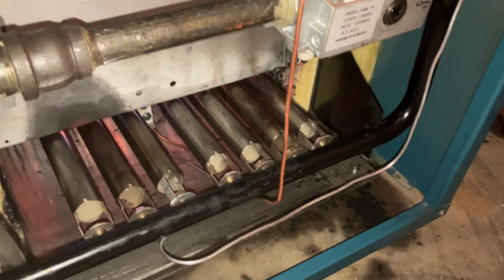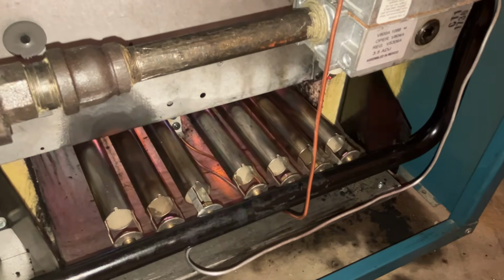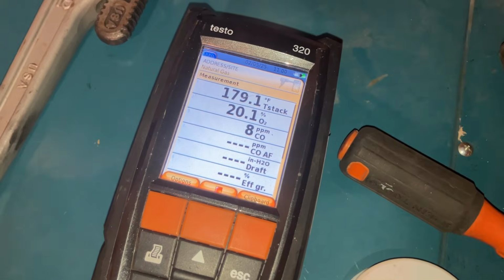And we got ignition. And now we check our combustion results after about 10-15 minutes. Ain't that crazy? 103 degrees, 104 degrees of stack temperature with just the standing pilot lit with 2 parts per million of carbon monoxide. Amazing, amazing. And it goes to show if you ain't testing, you're guessing.